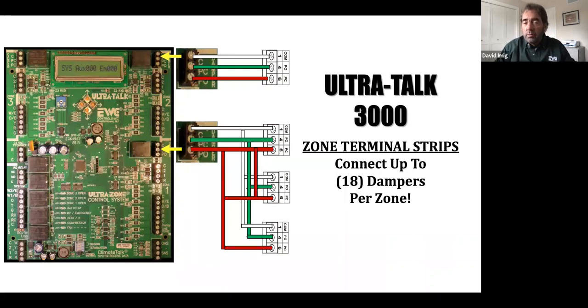An example of our dampers tied into this board. In zone 2, you see I'm just tying in straight one damper to one zone. Zone 2, 3 wires: power open, power close, and common. Zone 1, I've utilized the ability to have 3 dampers tied into my zone. I'm daisy chaining those 3 together and coming back to the panel one time. I can connect up to 18 dampers.